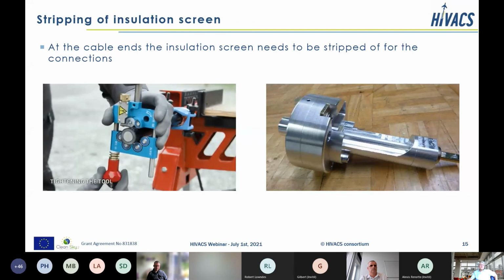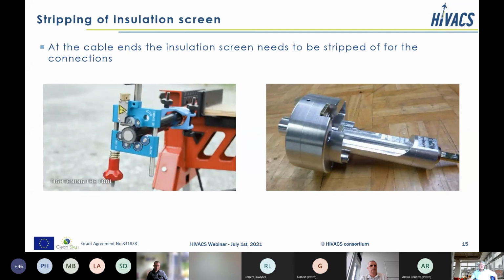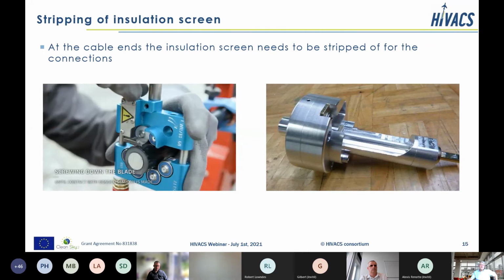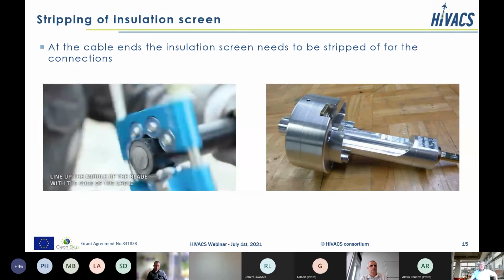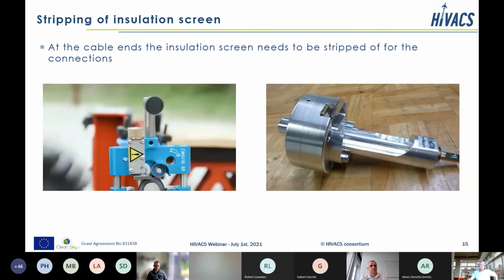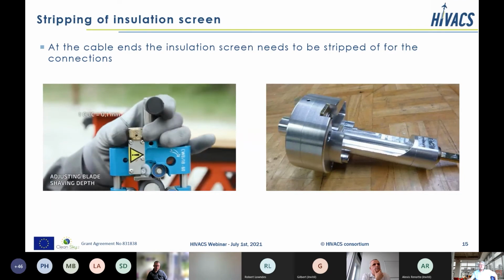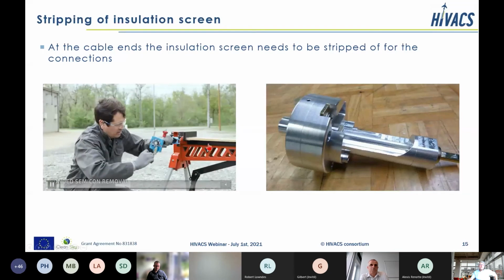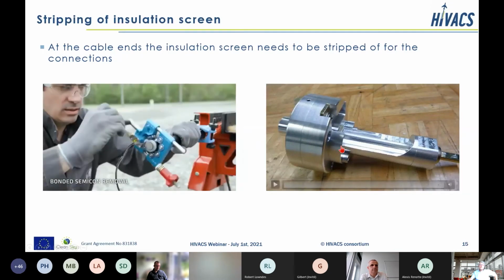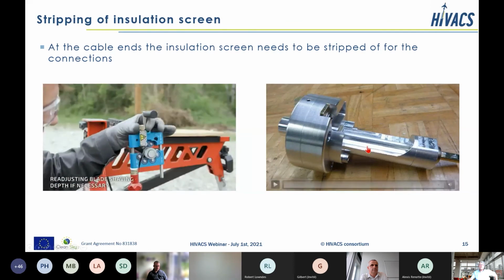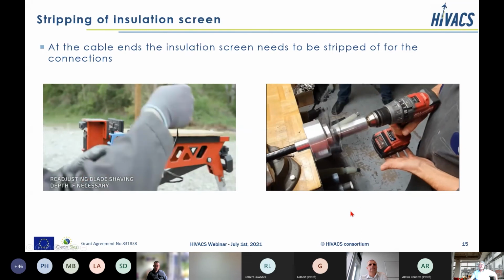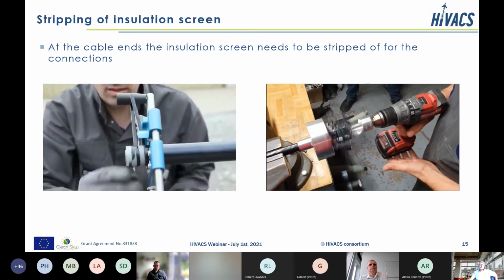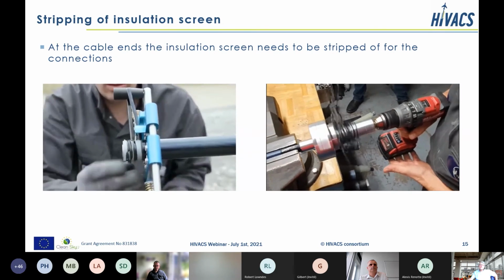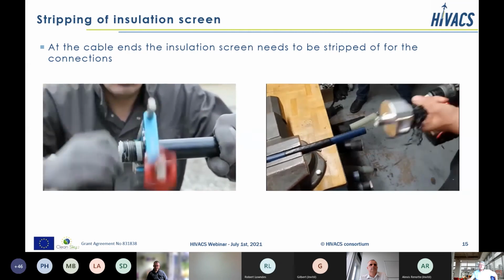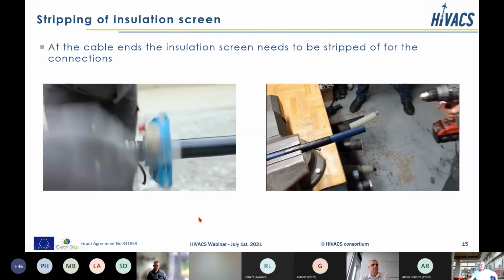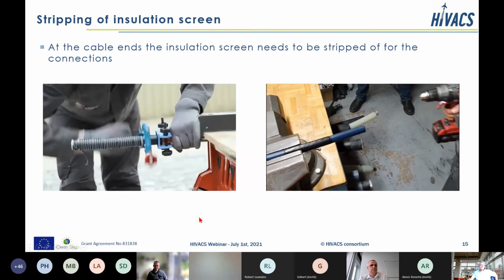And so here you fix the tool on the cable. Then you adjust the blade. And once you have adjusted it to the cable diameter, then you have to adjust the depth of the blade for the shaving. On the other side, you see a tool which is suitable just for one and the same cable diameter. Of course, in that case, the setup is quite quick, and you can use it together with a drill. And you see here the video where the semiconductive layer is stripped off. And there on the left-hand side, you see how the semiconductive layer is peeled off with the manual system.